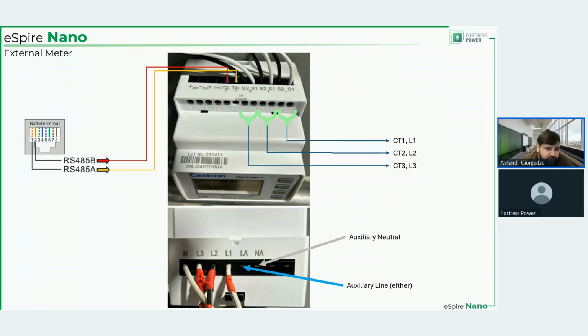You see neutral, L3, L2, L1. So L1 must coincide with the CT1, L2 must coincide with CT2, and L3 must coincide with CT3. And also, these must coincide with the rotation that you have on the grid input of the inverter. That's why I said that grid input is very important, that it falls in the correct rotation category. And also, it is not connected here because this photo was taken before I did so.